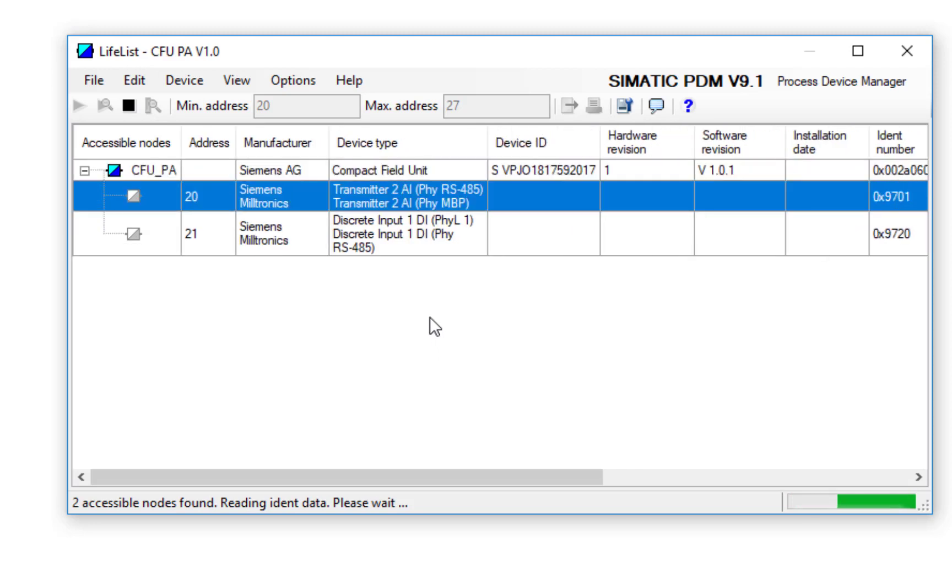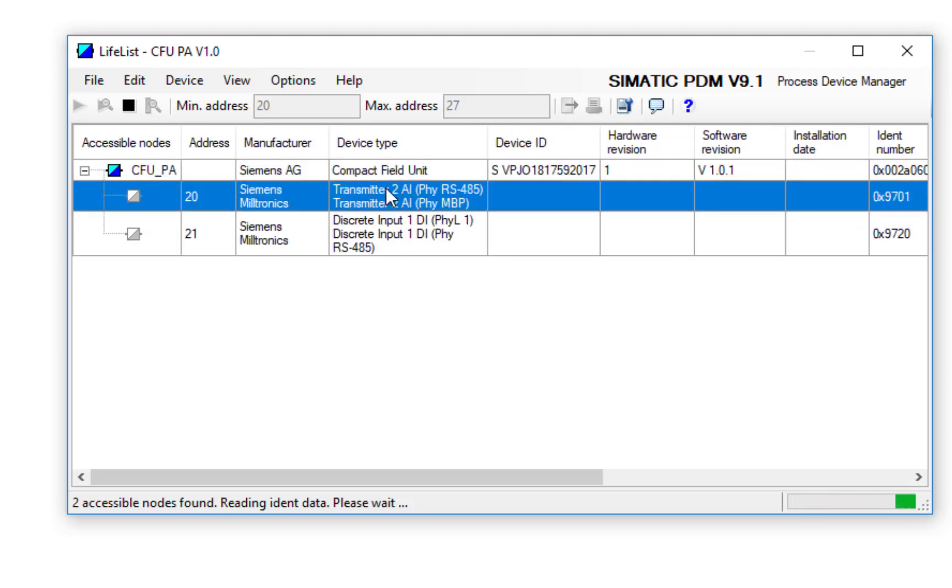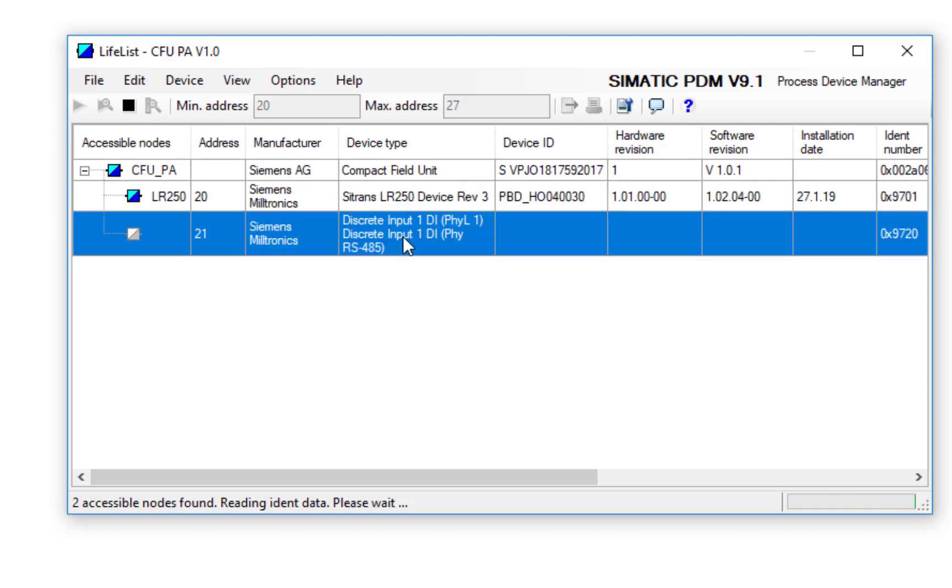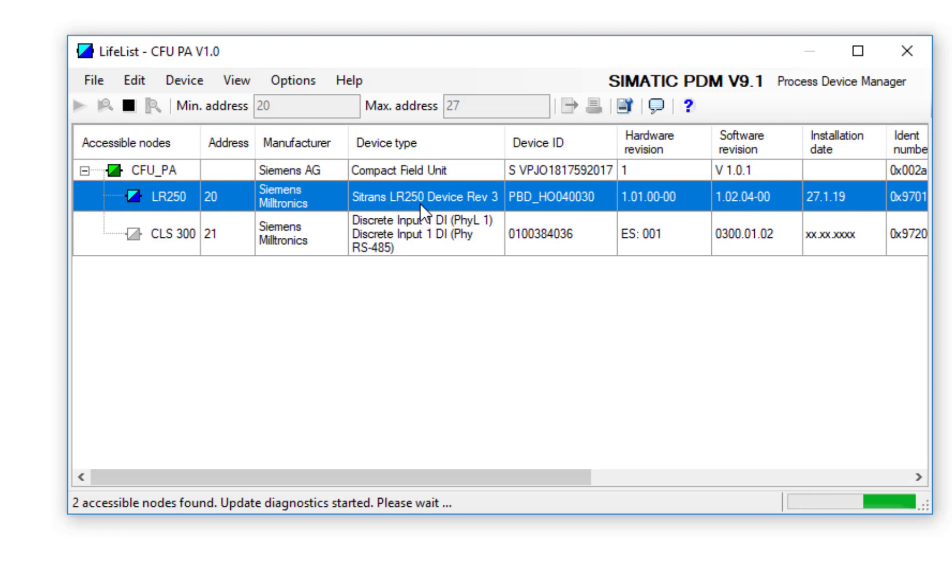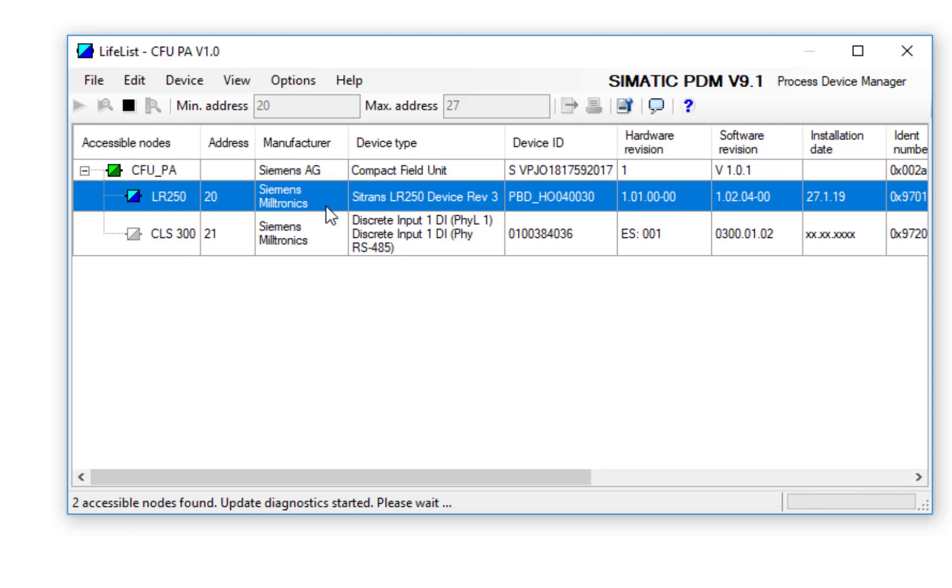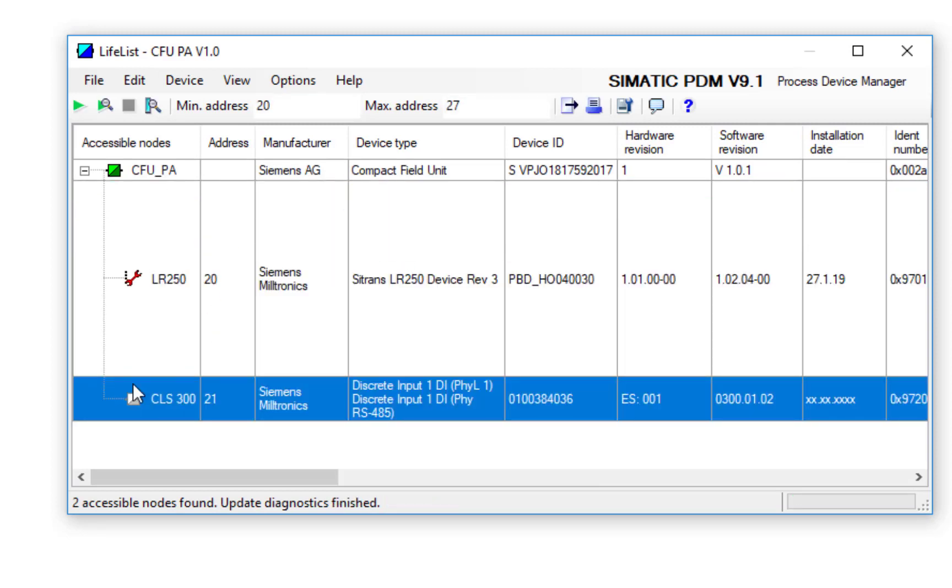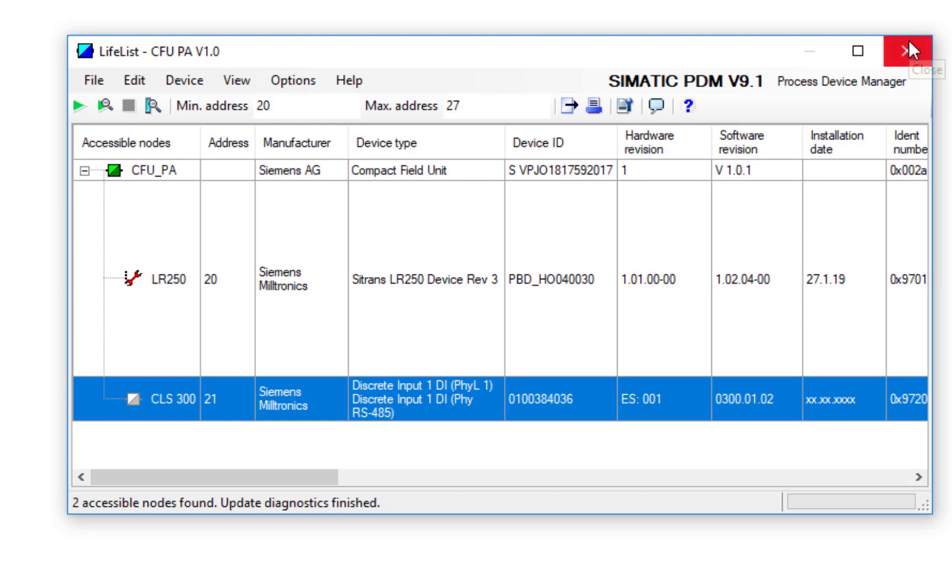Now, the generic GSDs are being used because that's the way this device works. But what it's going to do is read the six-digit or eight-digit code from the device so I get an idea of what it actually is. So I can see here that I have a CLS-300 on address 21 and an LR-250 on address 20.